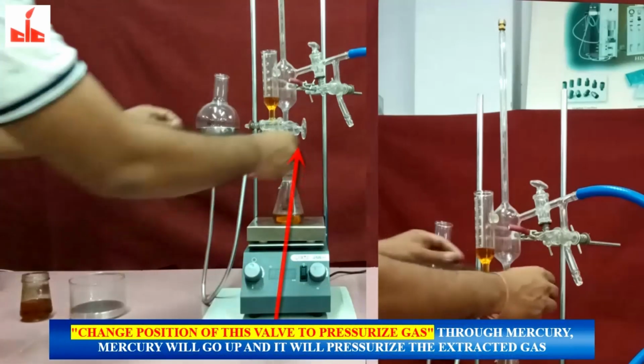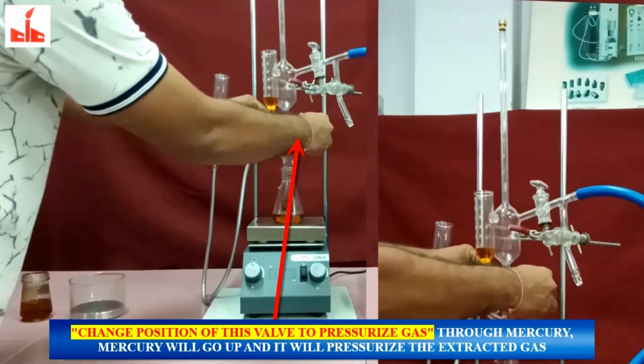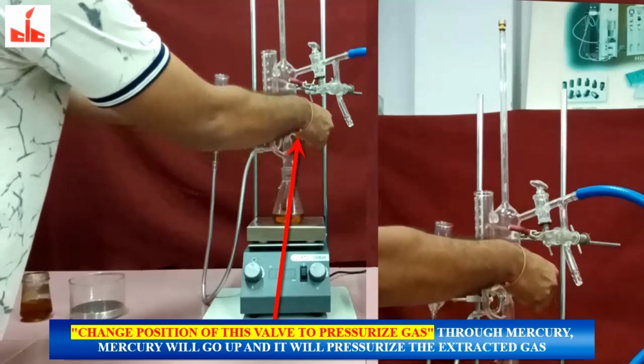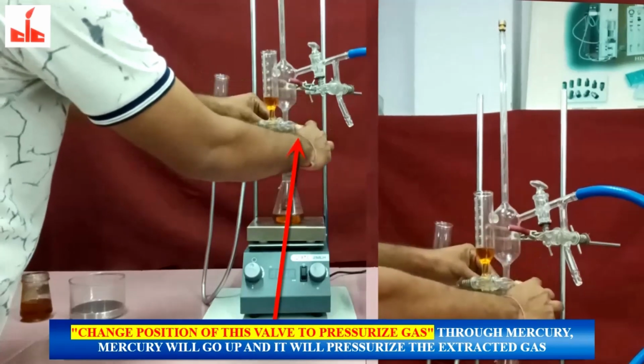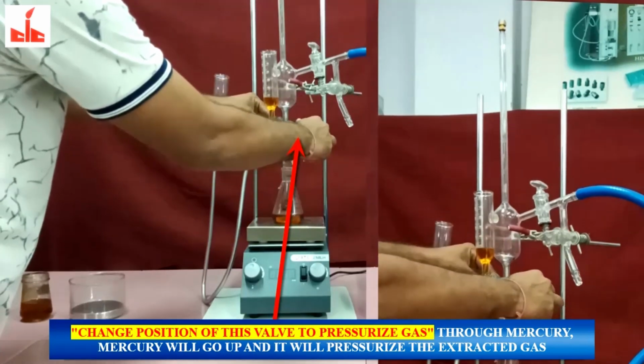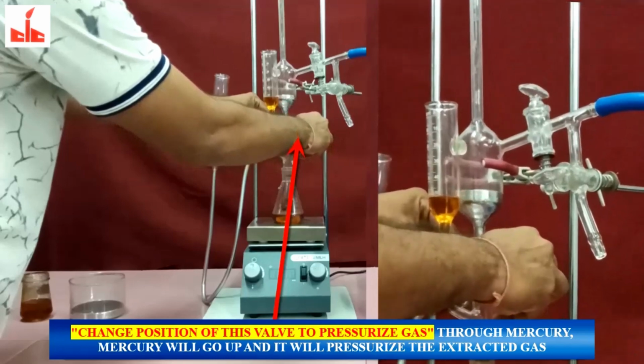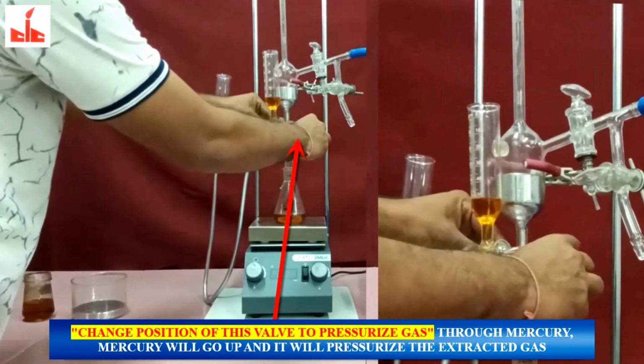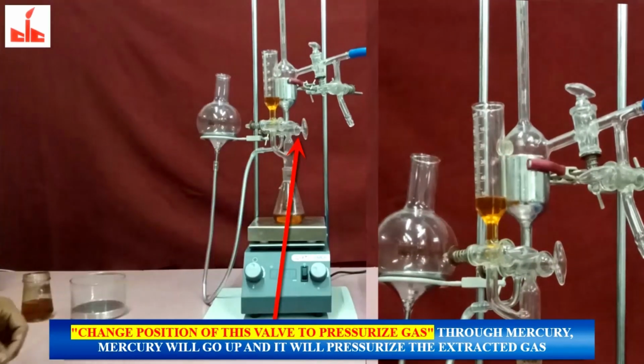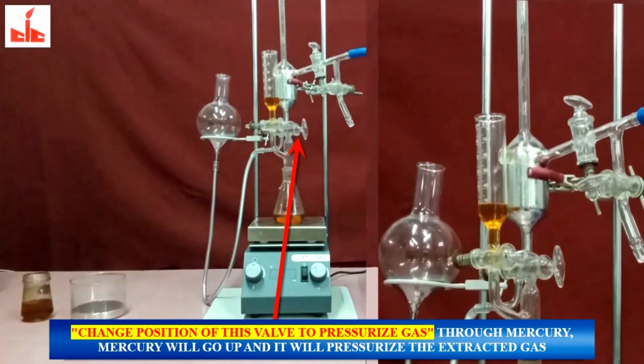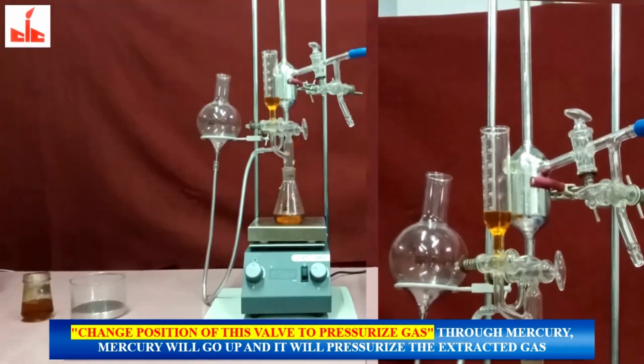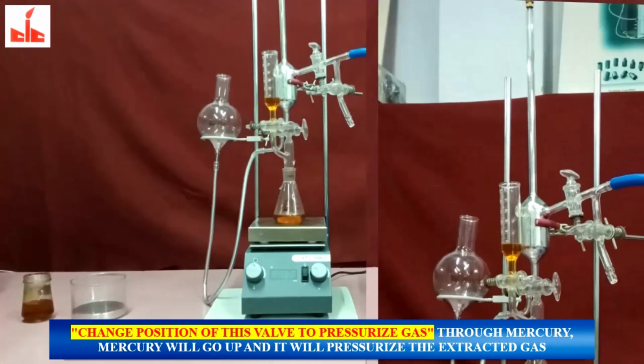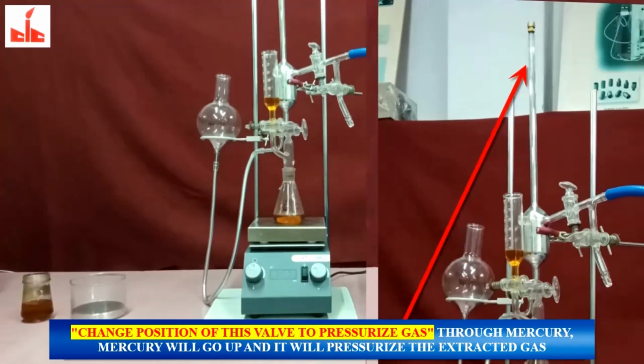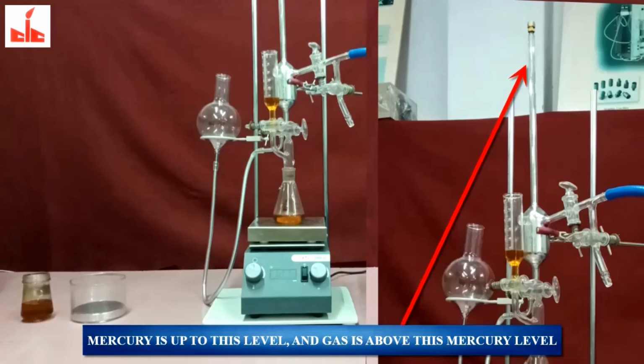Change the position of this valve slowly to pressurize the gas through mercury. Mercury will go up, and it will pressurize the extracted gas. Mercury is up to this level, and the gas is above this mercury level. The extracted gas is ready for the injection.